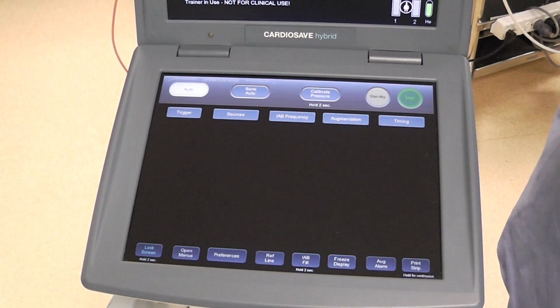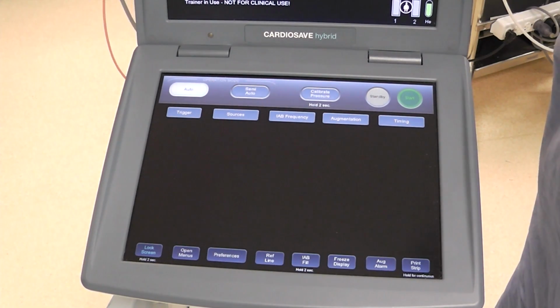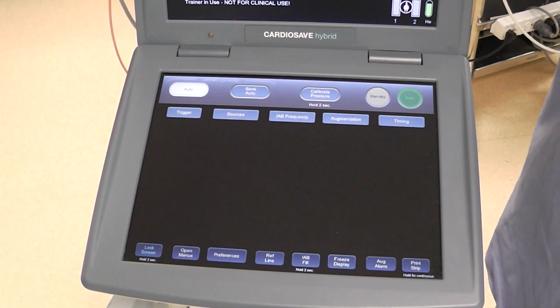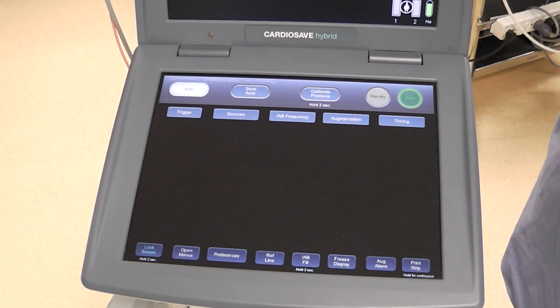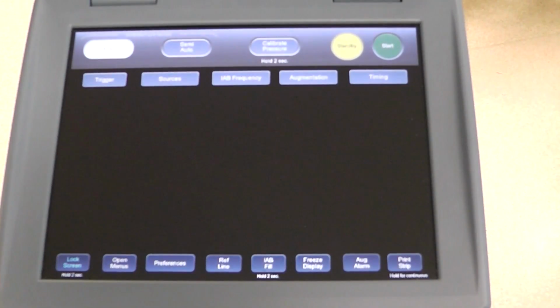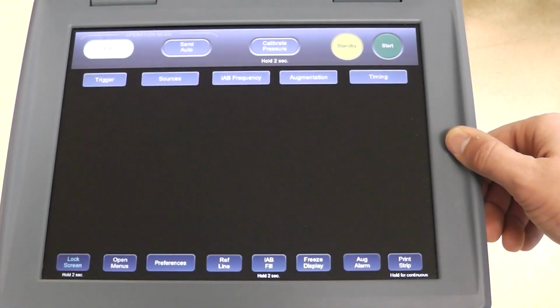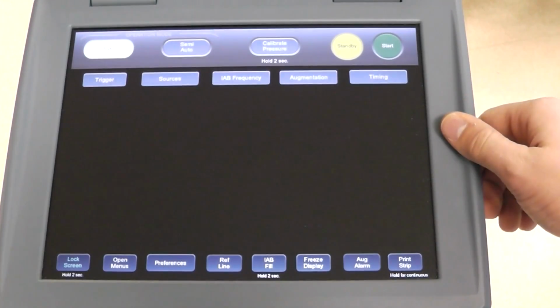Next thing we're going to look at is fine-tuning this so that you have the most efficient use of the balloon for the patient. So to fine-tune the balloon so that it's the most efficient that it can be for our patient, we're going to want to manually change some settings. And it's a little difficult because of the way these screens are angled to show both at the same time. So I'm going to go through the lower screen settings, and then I will show you what happens when you manipulate those settings on the upper screen.